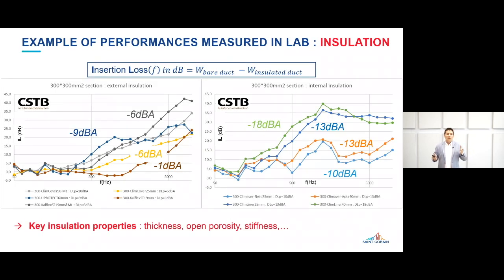What you can hear is that every insulation you put around the metal duct has an effect, giving a reduction of the noise. You can see the graphs on the left, done by an external laboratory. We can achieve with external insulation a decrease of between 10 and 1 dBA, and with internal insulation from 18 dBA to 10 dBA.